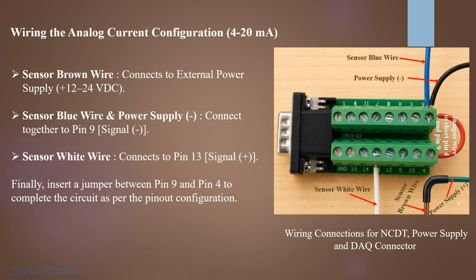Step 4. Wiring the analog current configuration. Make the physical connections as shown in the diagram on the right. First, connect the sensor's brown wire directly to the positive lead of your external power supply. Next, connect the sensor's blue wire and the power supply's negative return wire together into pin 9 of the DAQ connector. Thereafter, insert the sensor's white signal output wire into pin 13, which serves as signal plus. Finally, install a shorting jumper between pin 9 and pin 4 to complete the circuit as per the pinout configuration.